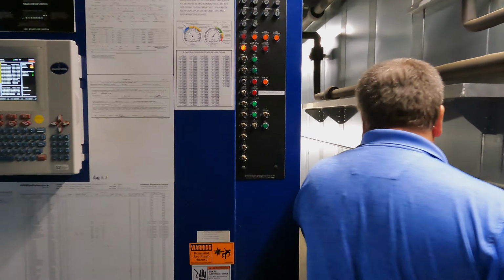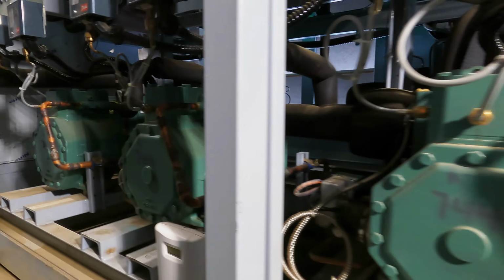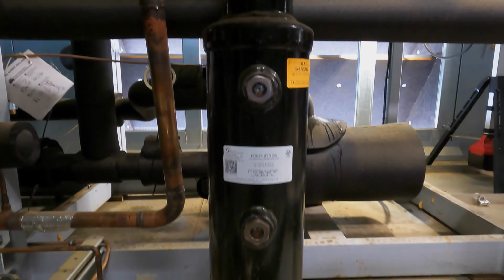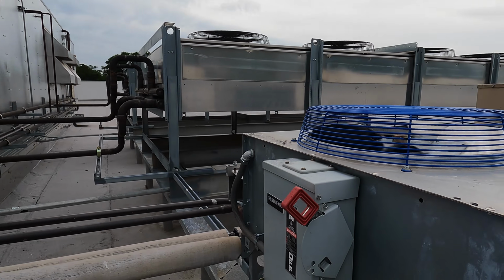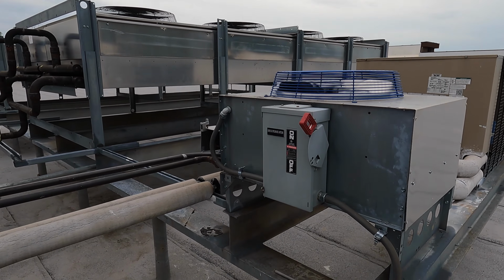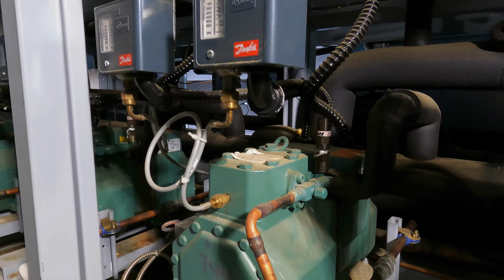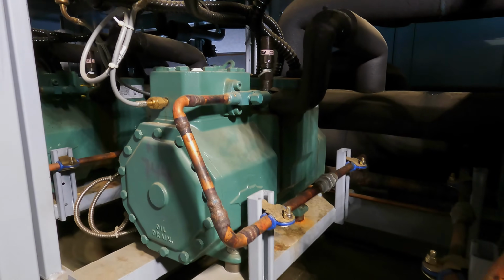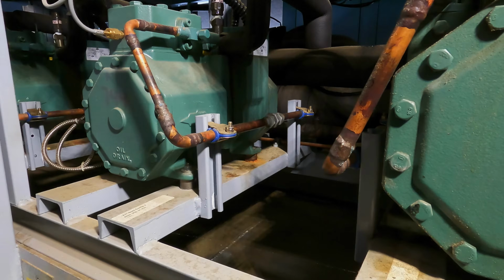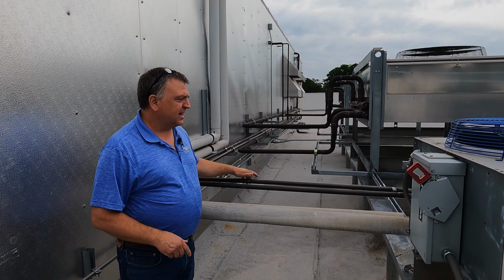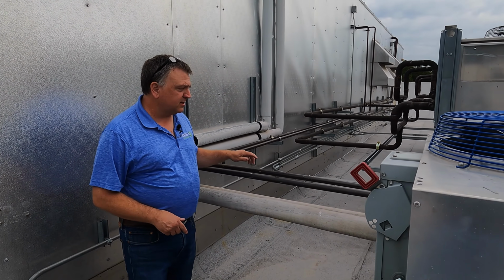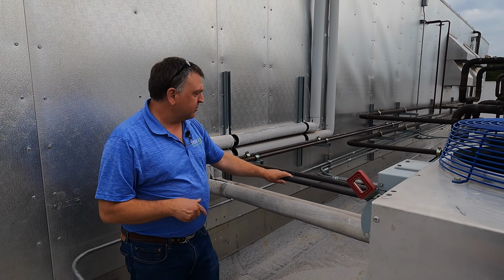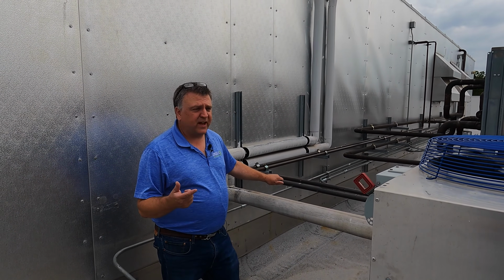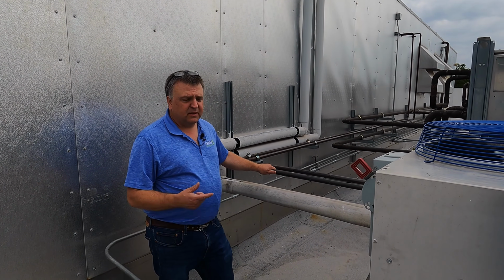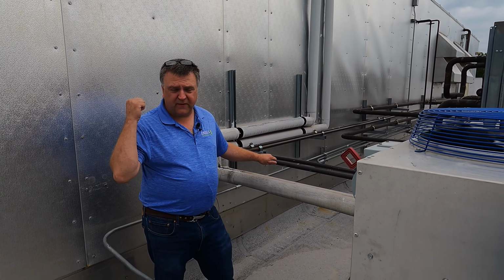Then the CO2 compressors bring the vapor in, of course compress it, and it goes through the discharge line, through our oil separator. The discharge line goes out to a device we call a de-superheater. Basically, what the de-superheater does is remove all the excess heat created by the compressors before it goes to our condenser. I can feel that. That's a cool line. That's a hot line. So that's our discharge coming from the compressor. And this is the return going to the compressor. It's still a discharge line and it's strictly vapor. All we've done is remove the excess heat before we introduce it to our condenser evaporator inside.